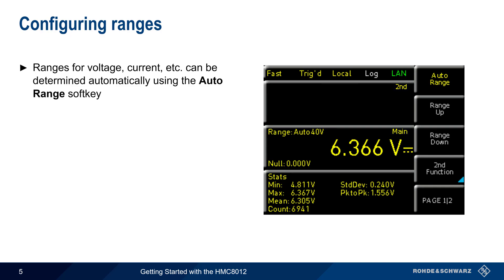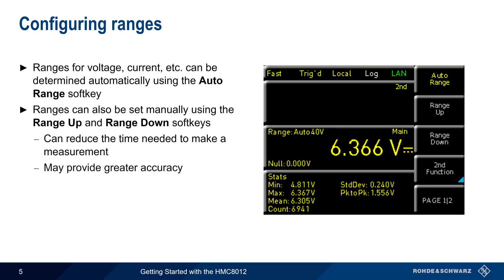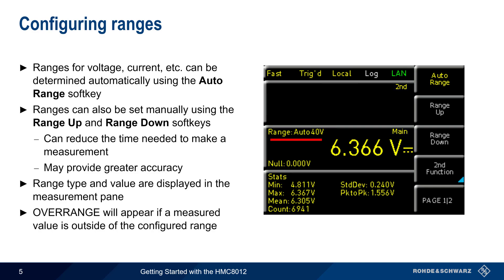Most multimeter measurements require a range to be set, and the easiest way to do this on the HMC is using the auto range function, which senses the measured quantity and sets the range automatically. Ranges can also be set manually using the range up and range down soft keys. Manually defining the range can reduce measurement time and may also provide greater measurement accuracy. The type of ranging and the range value are displayed in the measurement result pane, and the word 'over range' will be displayed if the measured value is outside of the configured range.